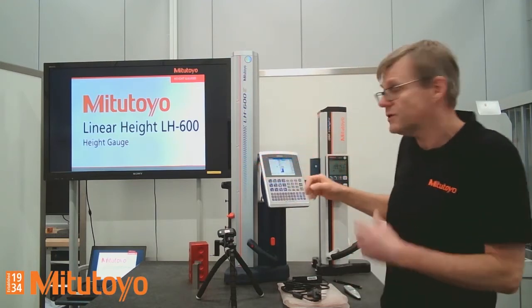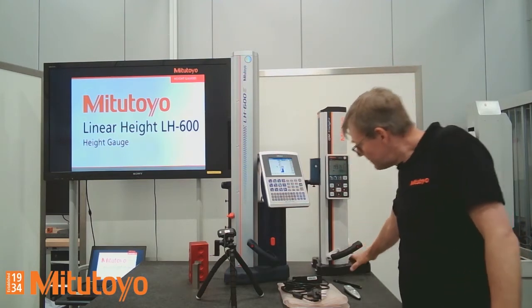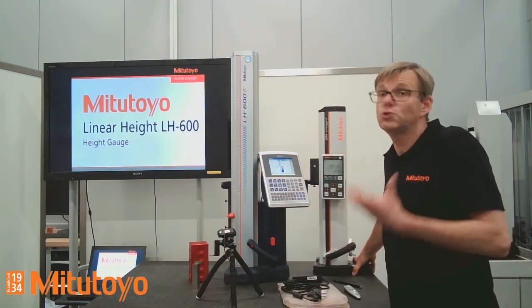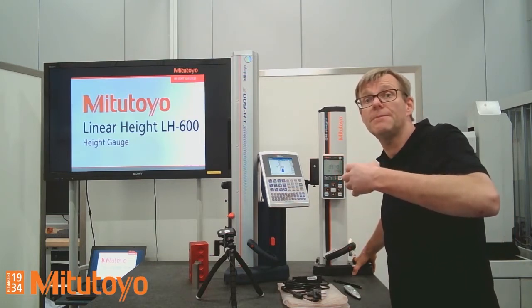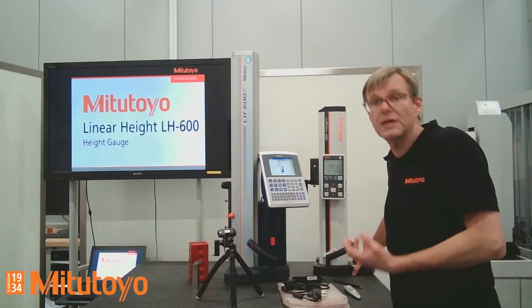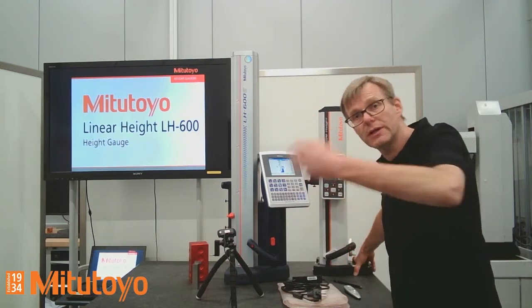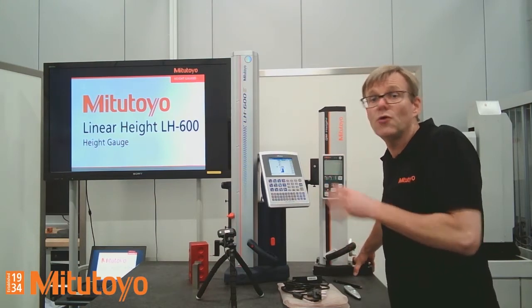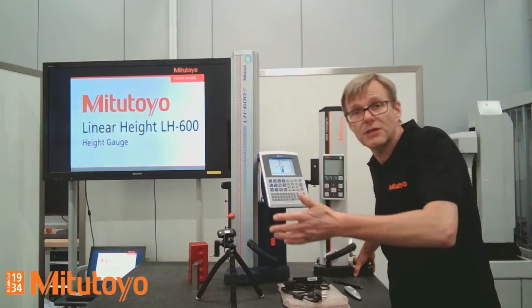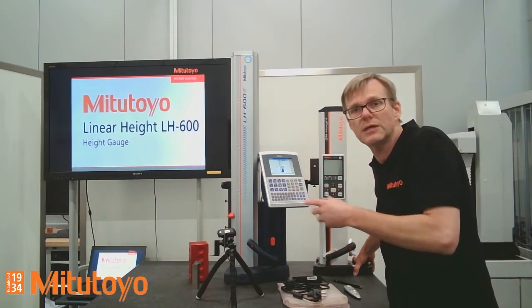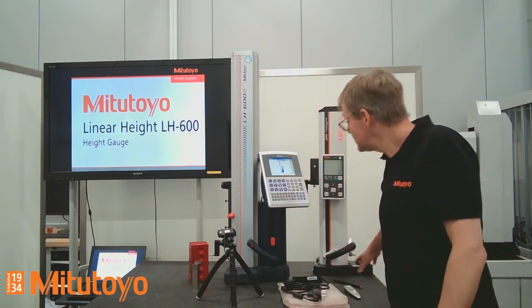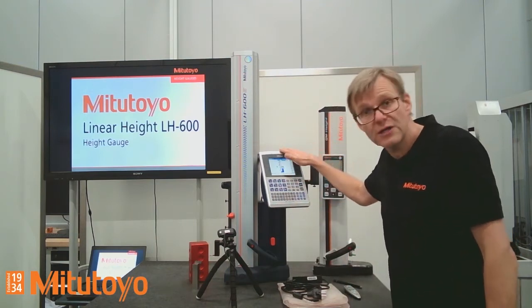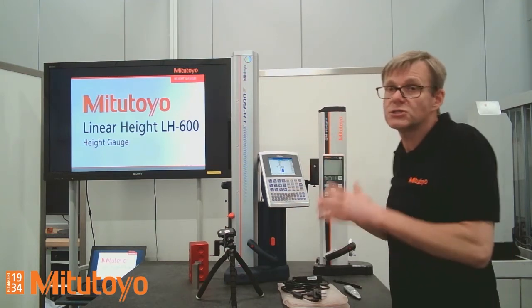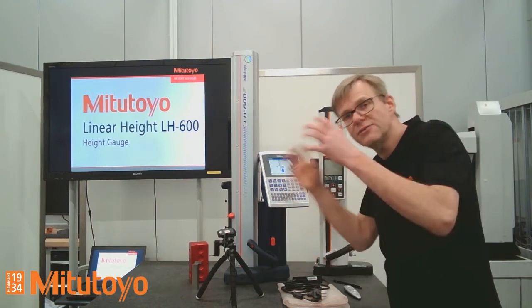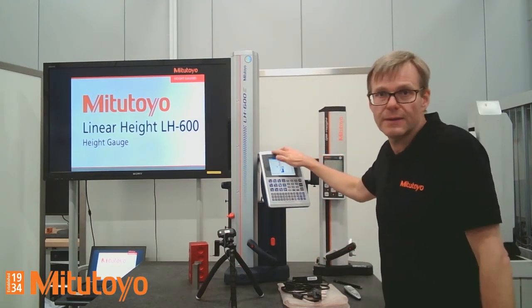Another difference is that with the QM Height, it's impossible to make 2D measurements, for example. It's impossible to make and execute part programs. There is no statistical functionality inside, and so on. This is purely for single measurements. For sure, you can make diameter and height measurements, and you can calculate the distance between two circles. But the functionality is much lower than this one here. So this is a multifunctional type, and the other is a standard functionality type. But this morning, I would like to concentrate on the LH-600, this one here.